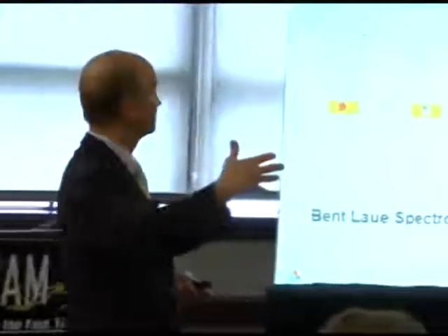And the beauty of this is Bruce and Jeremy did gold one day, platinum the next day, in the high-resolution XANES mode, and then they did resonant inelastic the third day. You can do many elements and many different kinds of experiments with a single spectrometer. So this is the prototype. This is sort of put together with spare parts, and it's not very pretty. Jeremy's in the process of building a more permanent and a more elegant spectrometer.